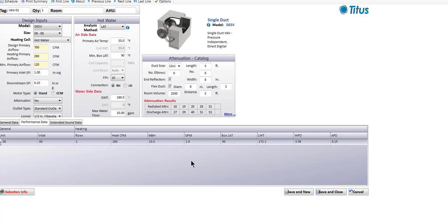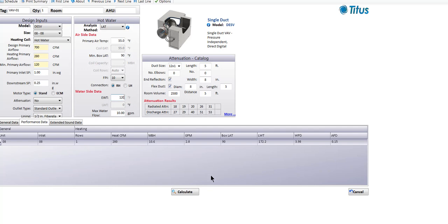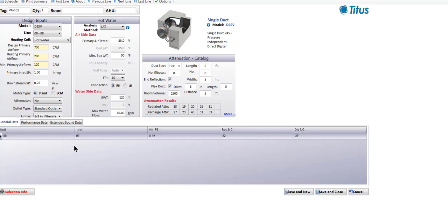Let's say we don't have 180 degree water. That's a big problem we're seeing these days — it used to be that the design temperature was typically 180 degrees, but nowadays with modern condensing boilers, a more typical water temperature is 120 degrees. We still need the same amount of heat, but less entering water temperature changes the requirements for this box. Reselecting at 120 degrees made a big difference: with no coil we had 0.02 air pressure drop, with a one-row coil it was 0.17, and now with 120-degree water we're up to a three-row coil at 0.49 inches — a pretty hefty air pressure drop.